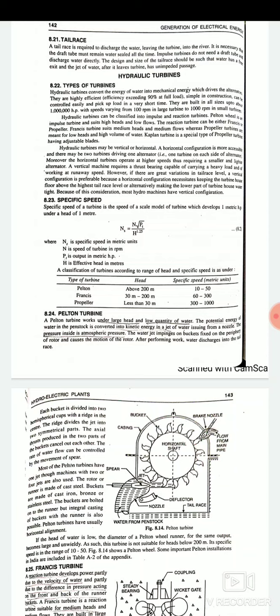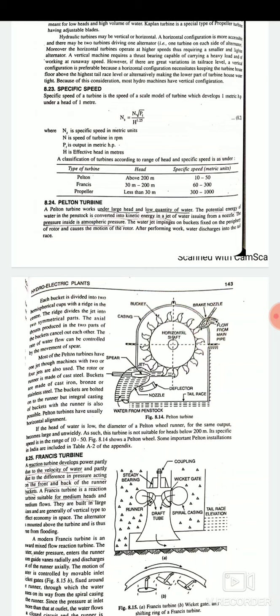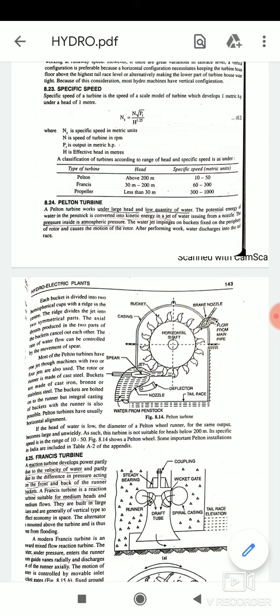Next is specific speed of the turbines. Specific speed of a turbine is the speed of a scale model of turbine which develops one metric HP under a head of one meter. The equation can be written as Ns equals N root PT divided by H power 1.25, where Ns is the specific speed, N is the speed of the turbine in RPM revolution per minute, PT is the output in metric, and H is the effective head in meters. So this is a table that describes the classification of turbines according to the range of head and specific speed. The Pelton turbine head is greater than 200 meter and the specific speed must be 10 to 50 metric units. The Francis have 30 to 200 meters, that is 60 to 300, and propeller that may be Kaplan turbine, that less than 30 meters, that is 300 to 1000 specific speed.